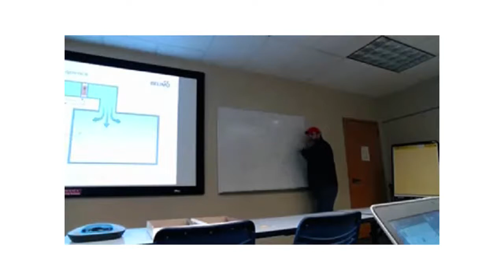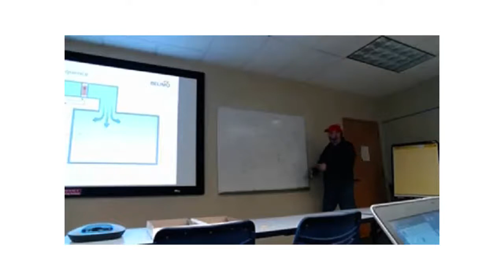So I don't know if you guys have these systems, but on data centers, anybody work on data centers at all? Okay. So in data centers, the typical criteria for data centers, unlike outside air, return air, things like that. The difference between this and this, something like that, 5%. So they want to know exactly where those outside air dampers are. They want to know exactly where they are. And so that's where feedback becomes important. On office buildings, not so much, right? I mean, we don't normally use feedback, but it's available on what we call proportional actuators, and we'll talk about that in a minute. So it's something for like the newer guys.